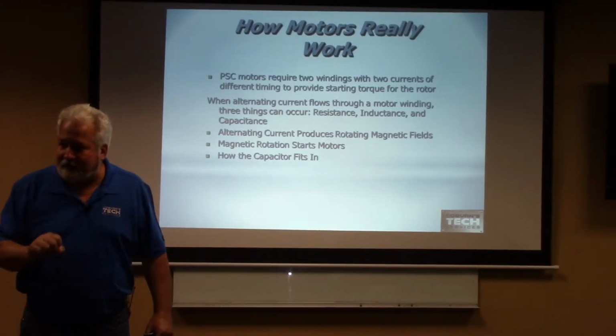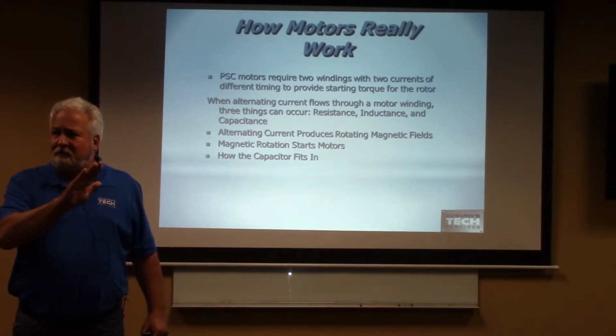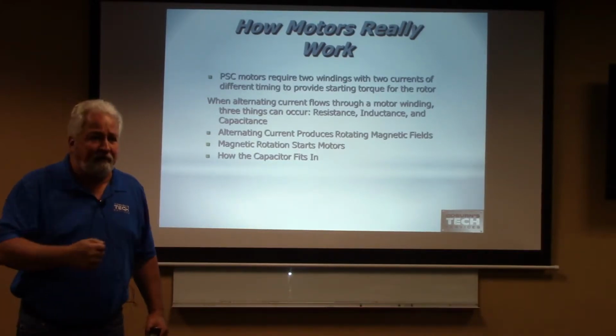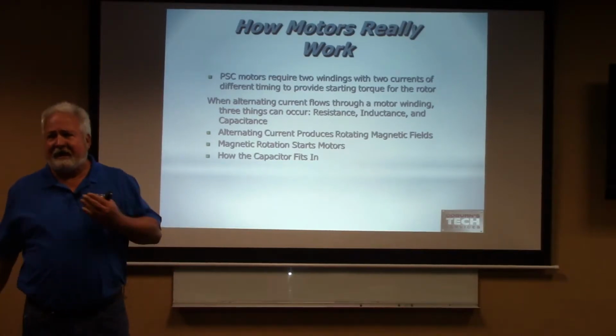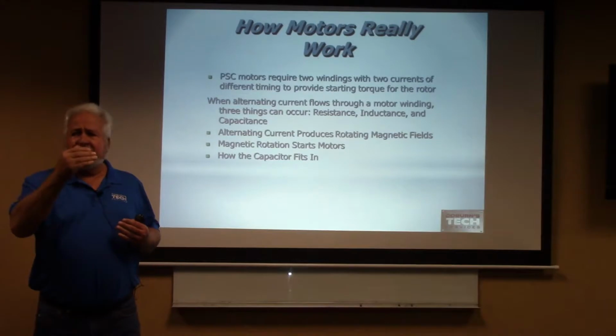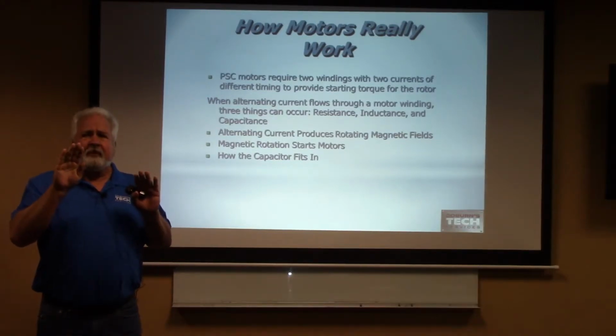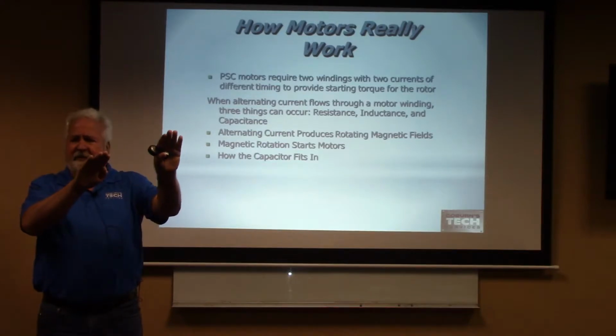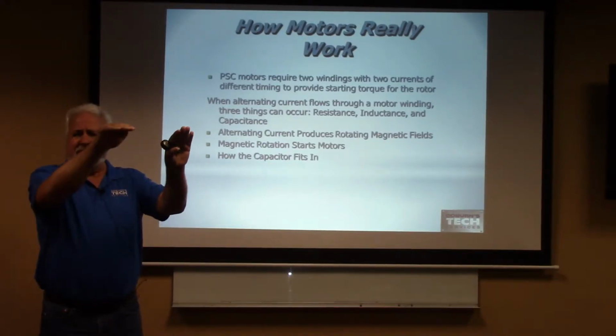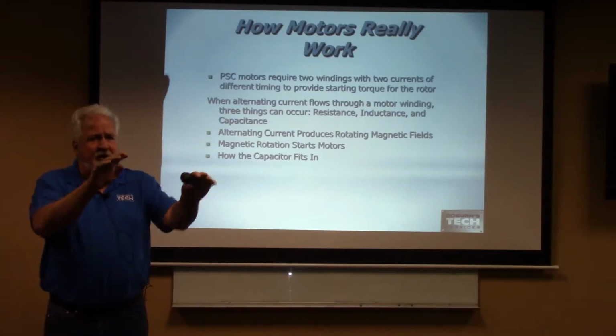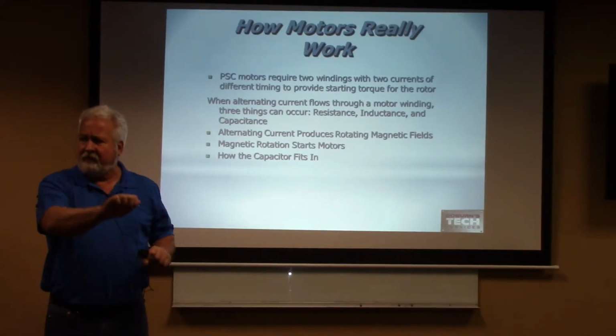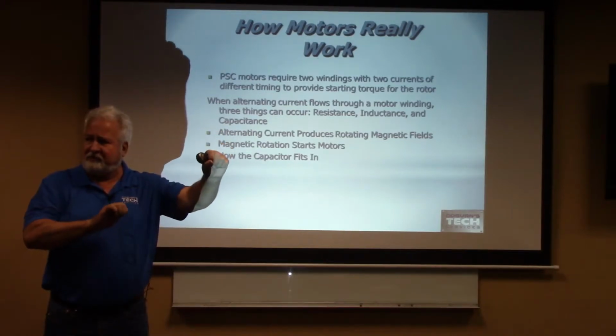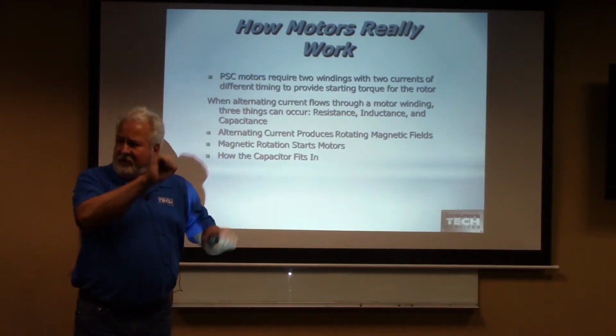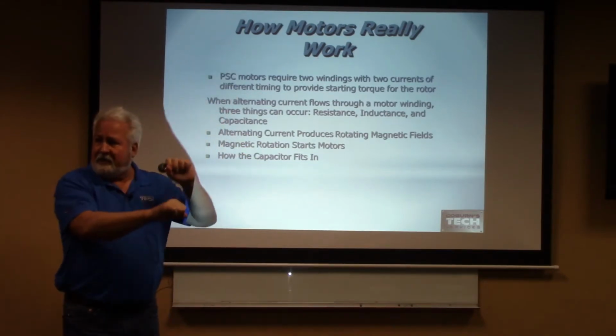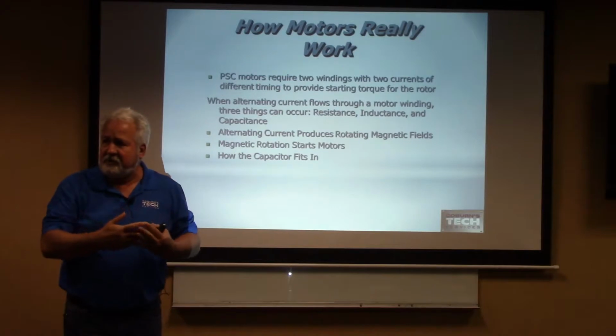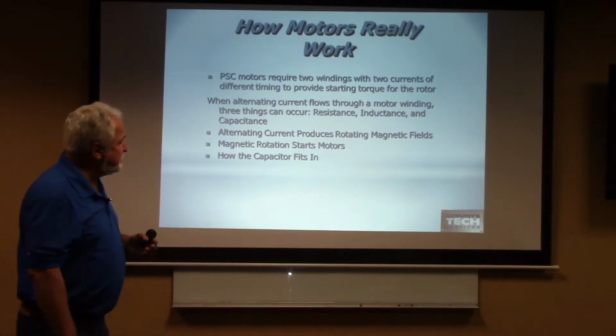You can pedal it, but as soon as you start to go uphill, it just doesn't work very well. When I add a capacitor to that run capacitor, it throws another pedal into the mix. Your voltage and your current just get shifted out of phase just enough where this one's hitting at a high point when this was starting to drop down. So it's kind of like adding that second pedal in there. It's a 2-phase motor. Does that make sense? Good. So now when I'm going uphill, it works out a little bit better. Does that make sense? Good. So as the resistance increases, having a capacitor in the circuit helps out.